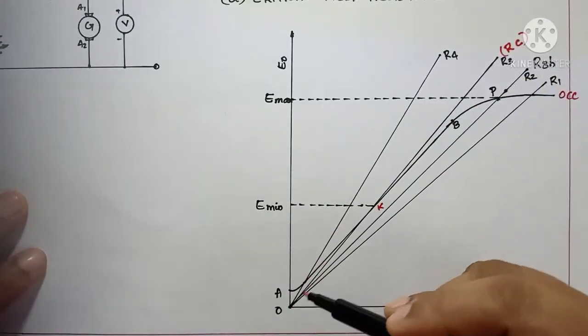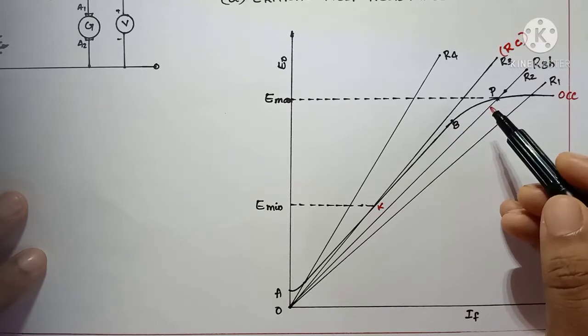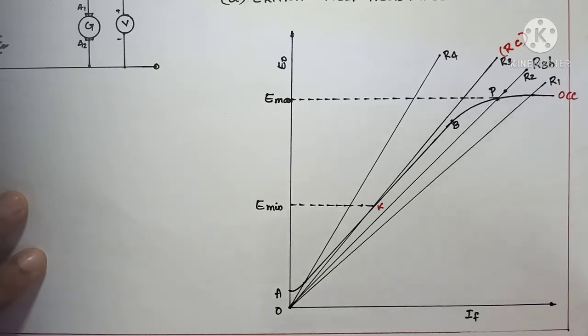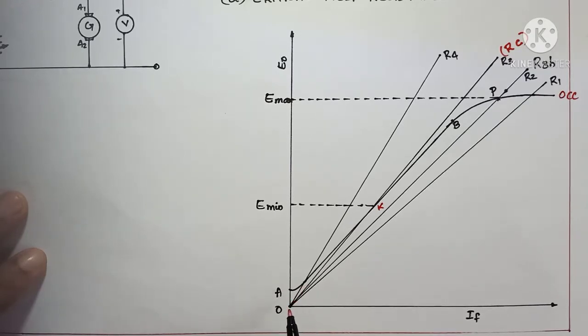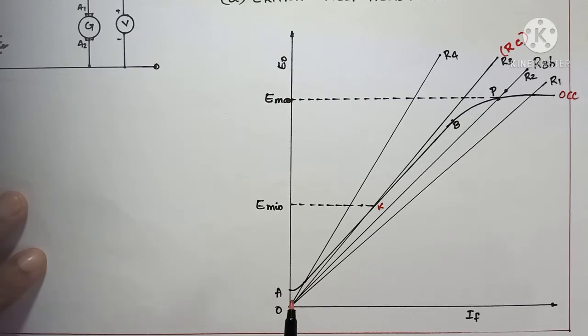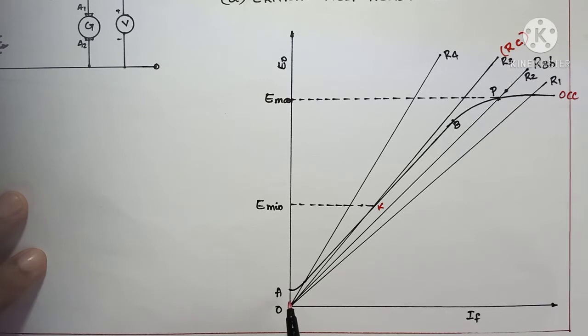From that table you can draw the open circuit characteristics. Here ABP is my open circuit characteristics. If the field current is zero, the voltage will not be zero — there will be some voltage in the generator due to residual magnetism. Even if the field current is zero, the voltage inside the generator will not be zero; it may be 0 to 5 percent or 0 to 5 volts or less than 10 volts. OA represents the voltage due to residual magnetism.